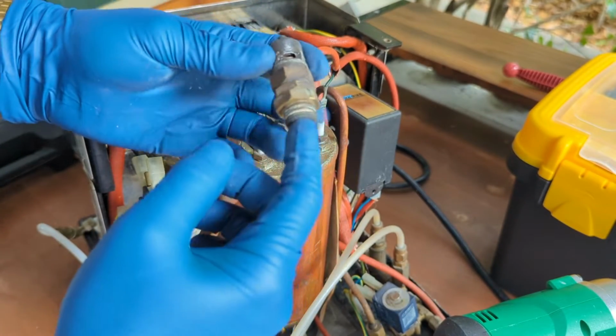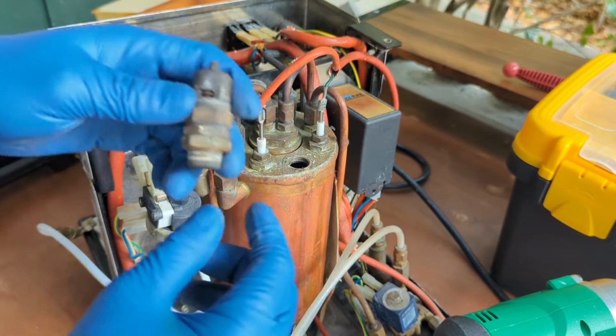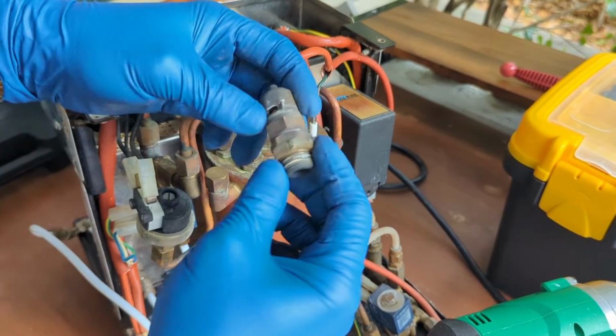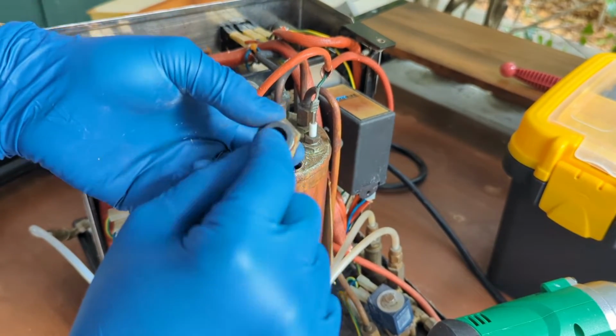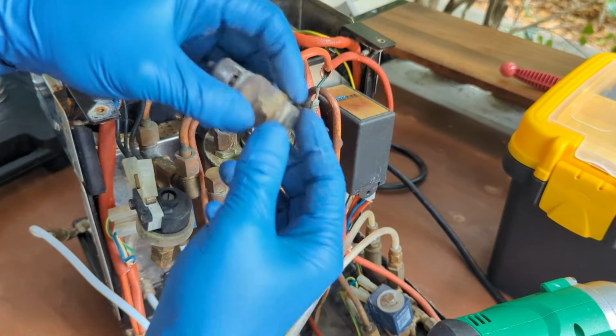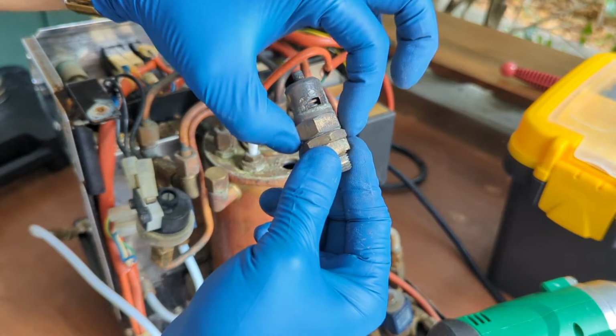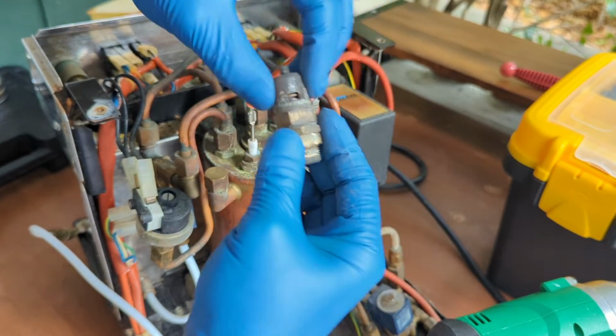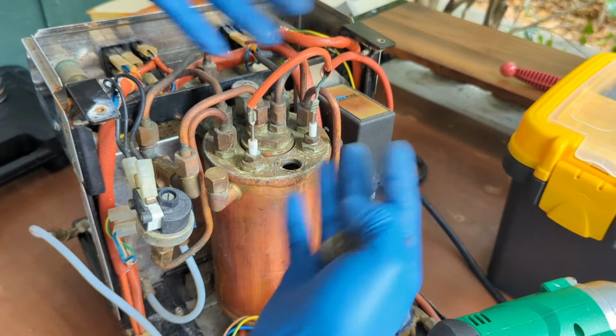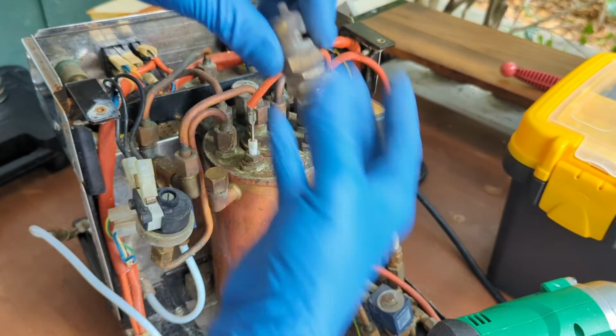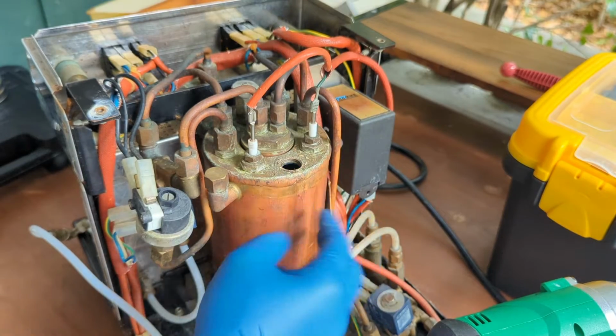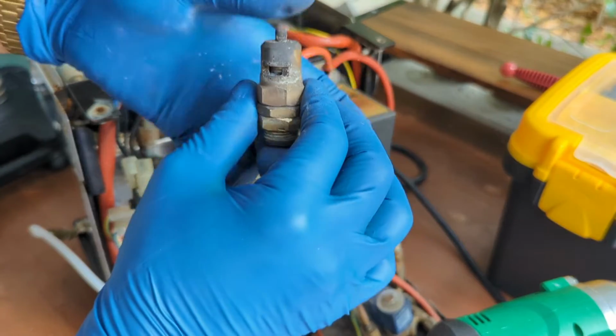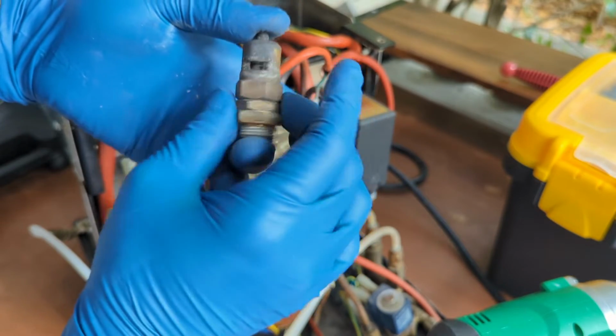The purpose of this valve is just to protect the machine from overheating. If there's a lot of pressure going through this hole, basically the pressure coming out from the boiler, then this will start pushing the spring and it will open up. Once it opens up, all the extra pressure is just gonna go and it's gonna pressurize back again to 1.5, or depending how this limiter is. Usually they are rated to 2 bars of pressure, 2.3 bars of pressure.